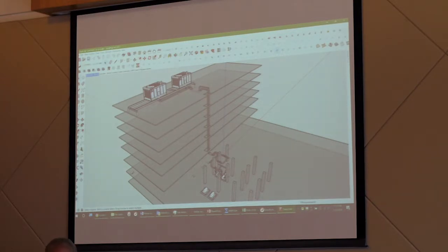Yeah, what is it? Anybody? It's quantity of lag on the condensing water side. Yeah, and it's a variable lag. So yeah, it's a big lag on the condenser water because at 200 GPM, if you do the math, if you take the volume of the pipe and all that stuff, it's like 15, 20 minutes for the water molecule to get from here over the tower and back at 200 GPM. At 3,400 GPM, it's a minute and a half.